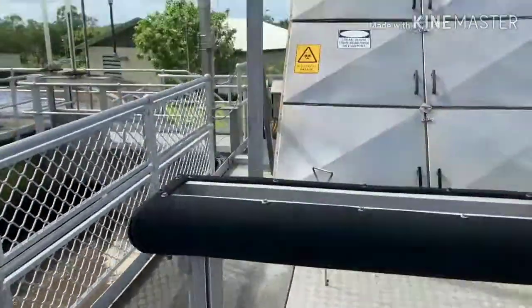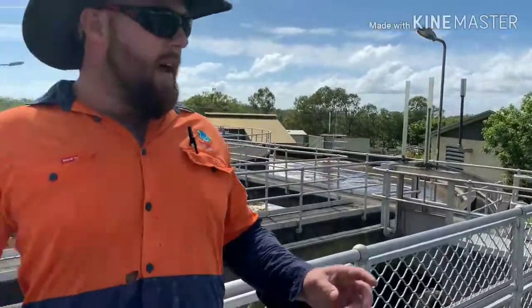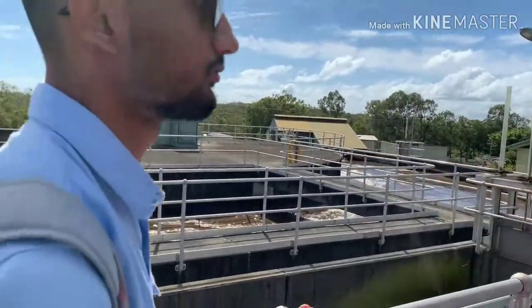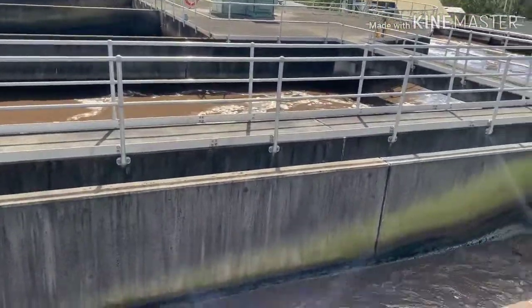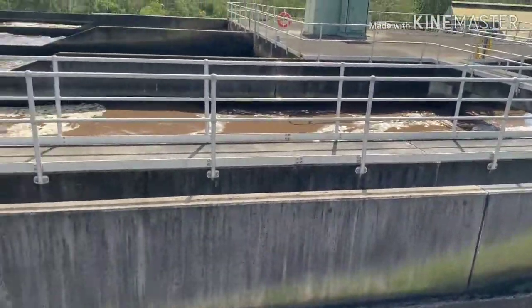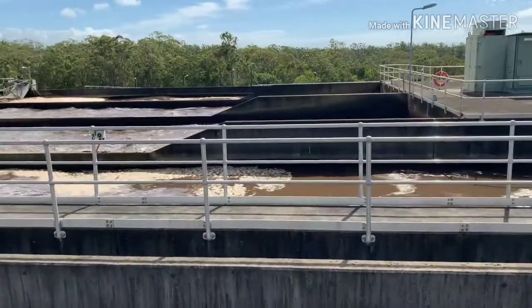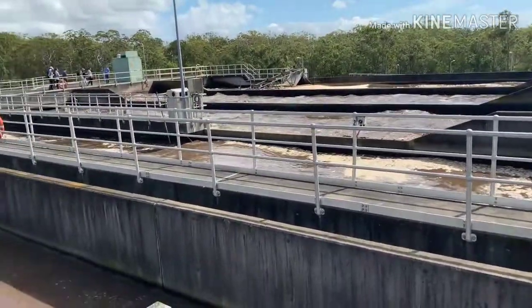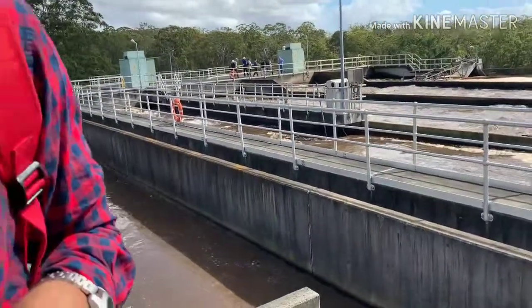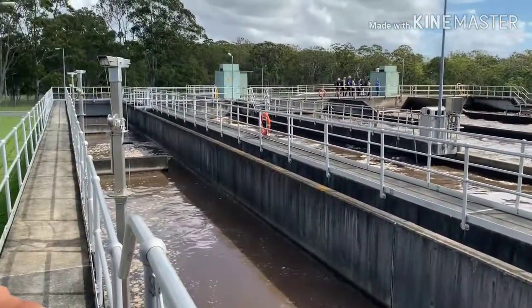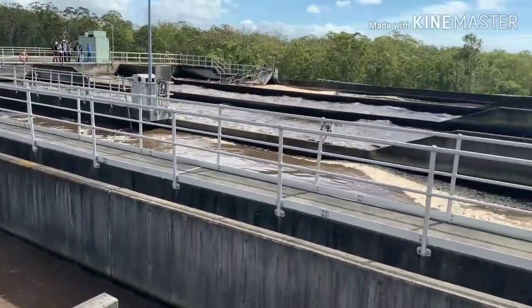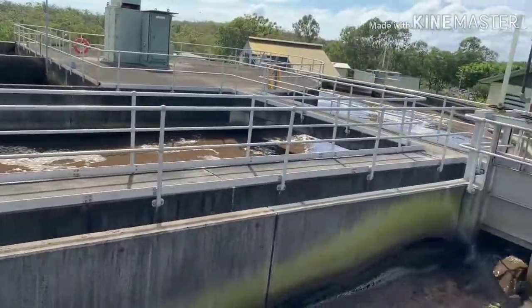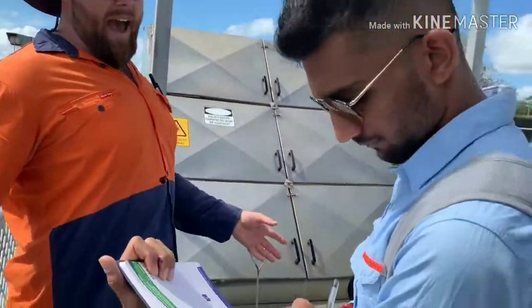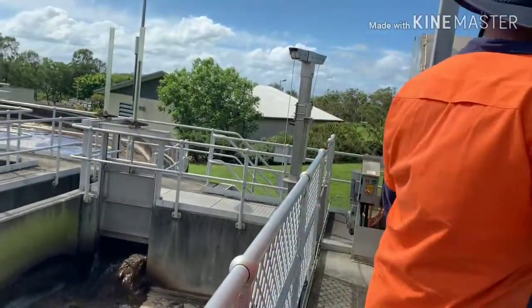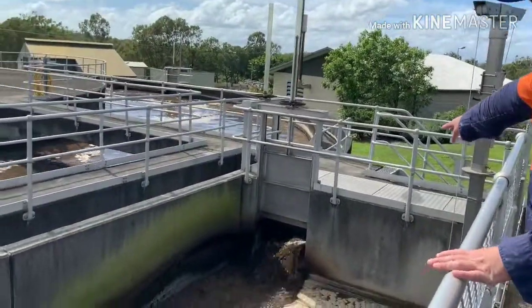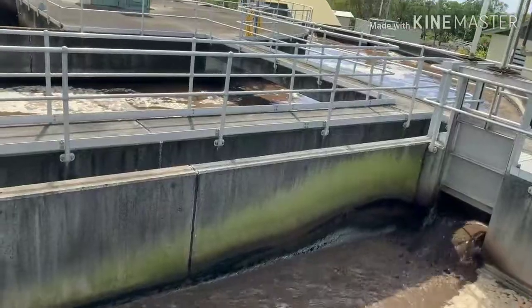Yeah, basically you've got your raw sewage coming in here, and your RAS return, which is the stuff at the bottom of the clarifiers, which you can just see the bridges over there. You've got your stuff that's settled out, that's coming back into here. Your raw sewage, and that's what we like to call mixed liquor. Okay, so mixed in there. You've just got a RAS screen here, so anything that comes back from the clarifiers, if there's any rag, it'll pick that up here.